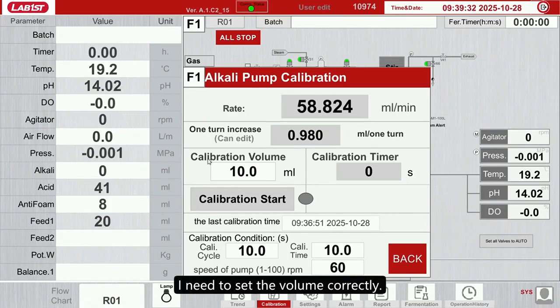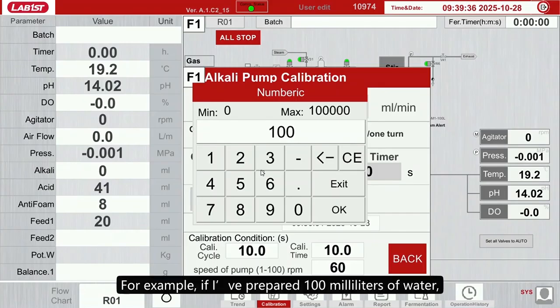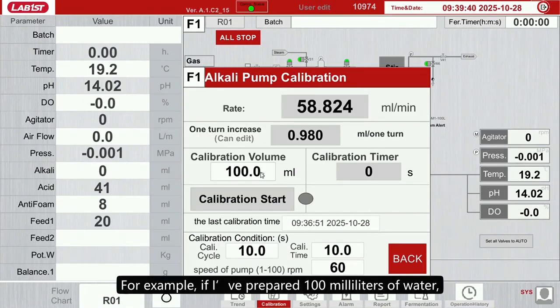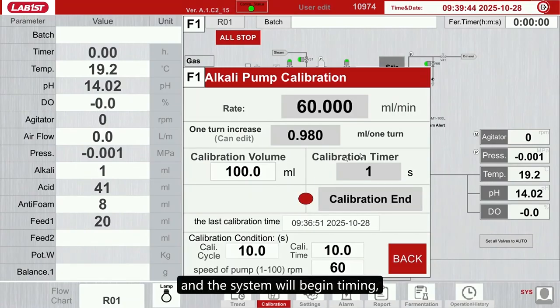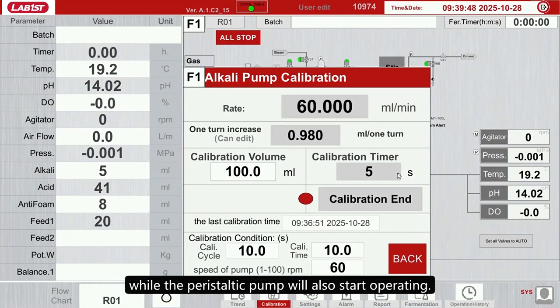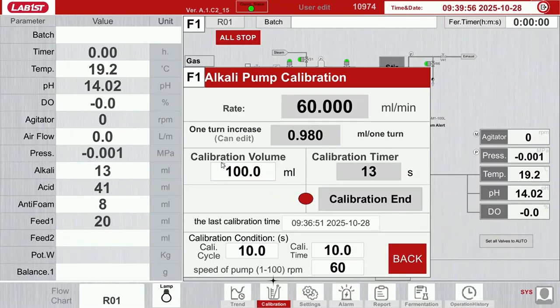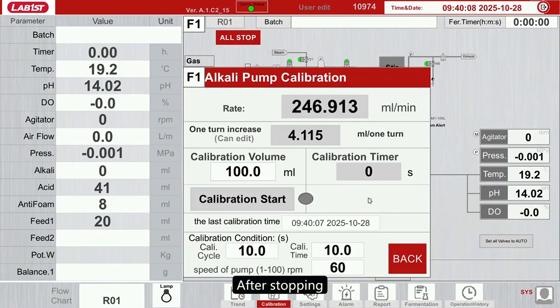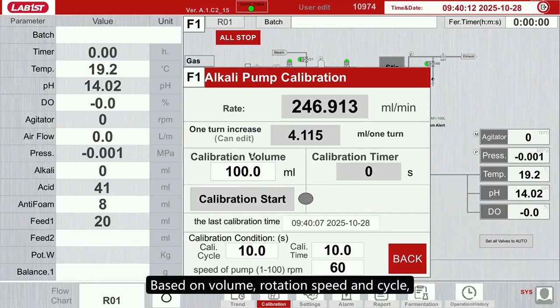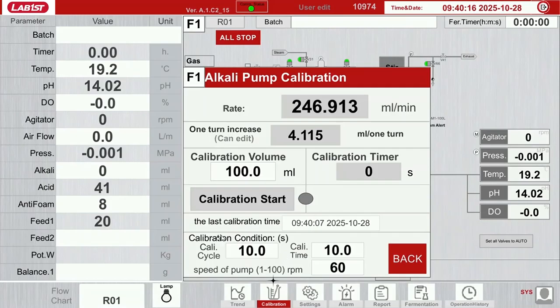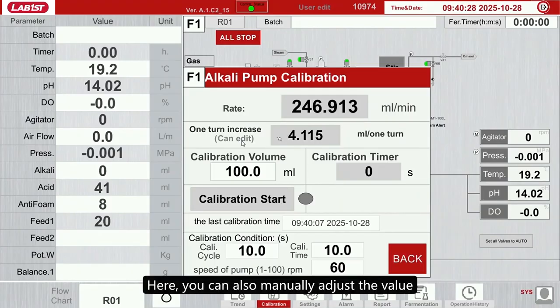Before calibration starts, I need to set the volume correctly. For example, if I prepared 100 milliliters of water, click Start, and the system will begin timing, while the peristaltic pump will also start operating. When you notice the water in the beaker is sucked up, we click Stop. After stopping, the pump will stop, and based on volume, rotation speed, and cycle, it will calculate a coefficient and finally determine the rate. Here, you can also manually adjust the value.